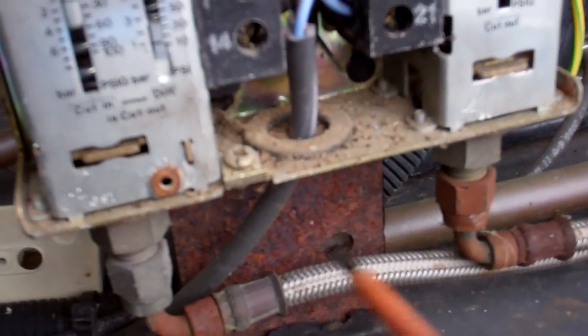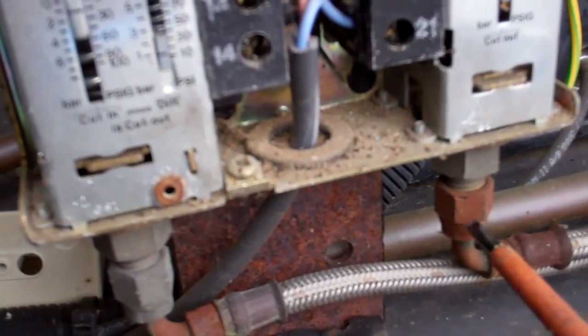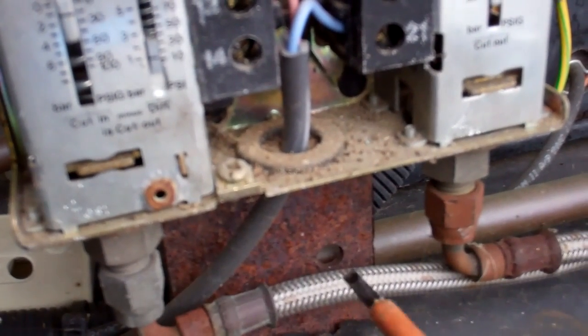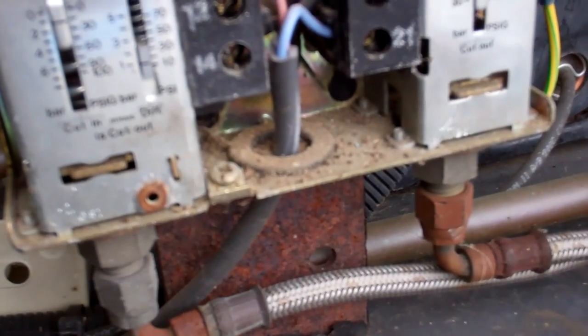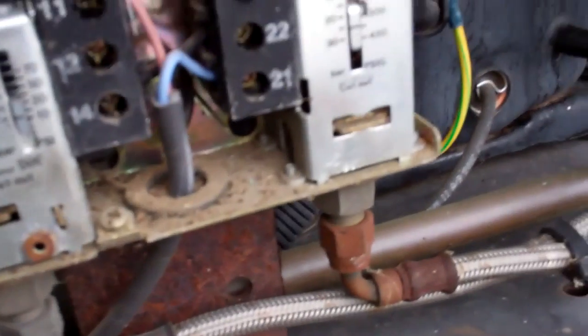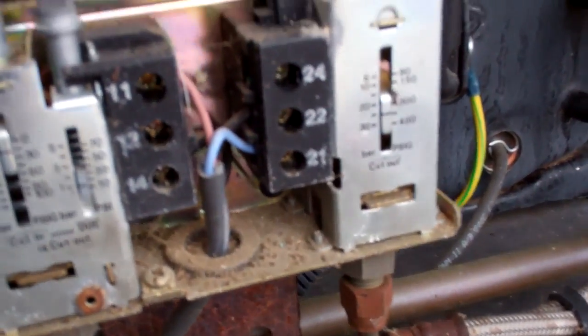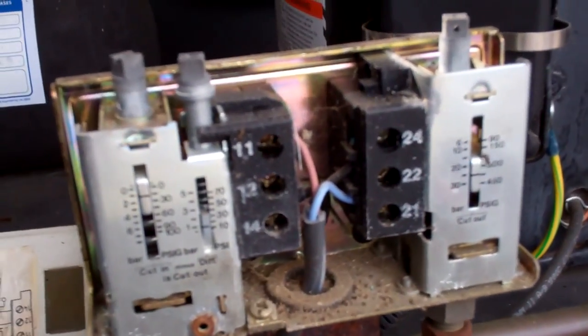If you just put the hoses on in the same place, you can end up with high pressure going to the low pressure and vice versa. And none of the safeties will do what they should do. I have seen that done. So that's something to be aware of.